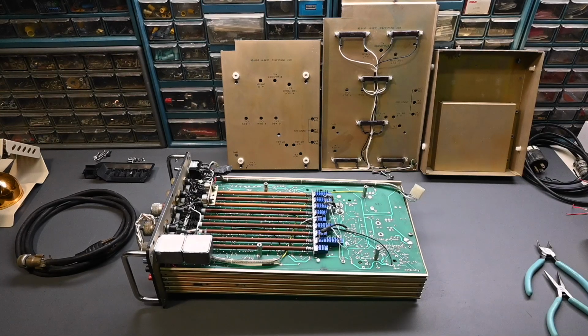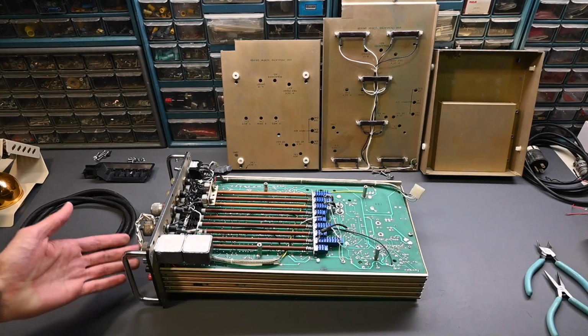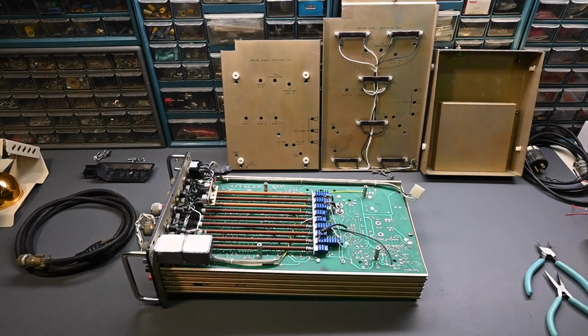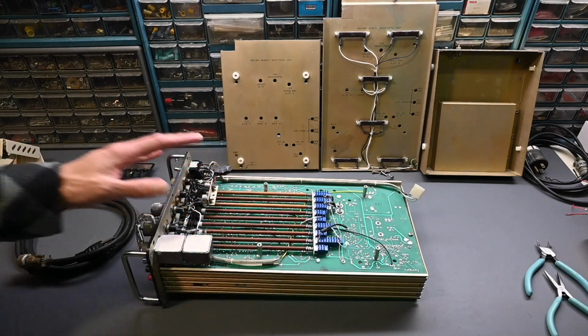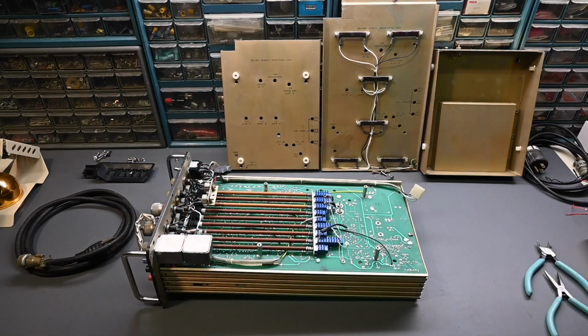I'm really getting suspicious about that calibration sticker on the front panel, because this meter does not look like something that was in the physical condition of an instrument that would have been calibrated. If someone did calibrate it, they really did a hasty job — the physical condition is like it was dropped or something. So I'm a little disappointed about the physical condition inside given that it had that calibration sticker. I've worked on other pieces of military surplus with those stickers, and when you open them up they're like factory new inside. Maybe I was just getting lucky on those, I'm not sure, but in this case it definitely needs some attention.